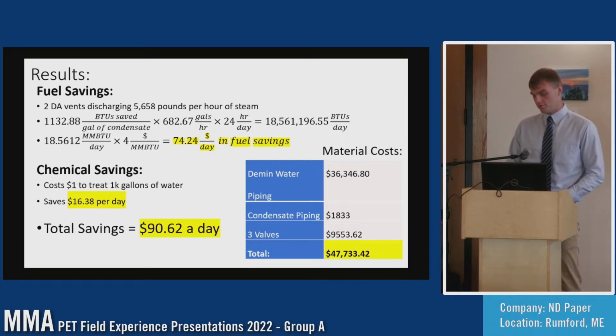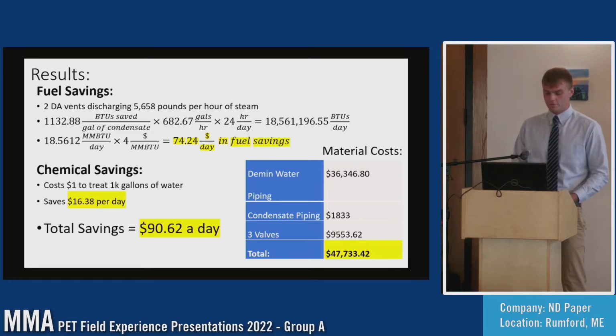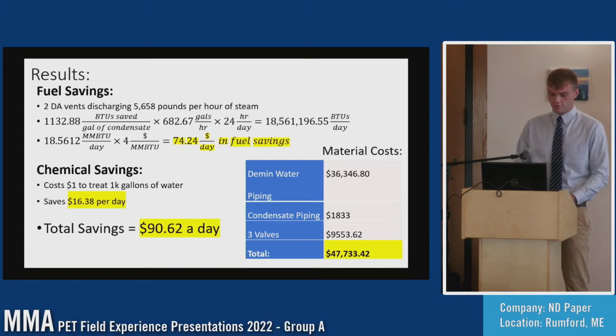And if you multiply that by 24 hours a day, we end up saving 18.5 million BTUs per day. And then our fuel cost worked out to be $4 per million BTU, which comes out to just under $75 a day in fuel savings. And then also we have chemical savings by not having to treat the demin water since it's already treated as condensate, and that saves an additional $16 a day, coming out to a grand total of $90 a day.